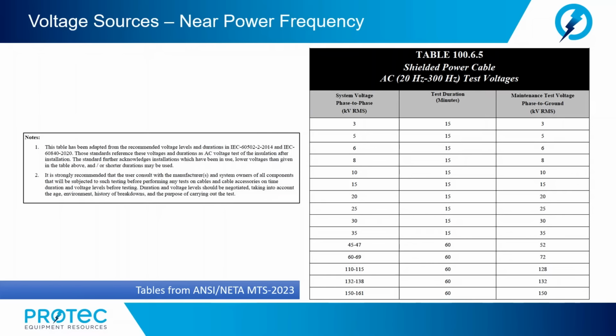And again, going back to the NETA tables that we find in the NETA literature, when we are dealing with medium and high voltage power cables, we do see that the near power frequency variety is called out in table 100.6.5, shielded power cables, AC testing, 20 Hz out to 300 Hz test voltage. This table is designed for the frequency-tuned near power frequency resonant test sets. And the test is typically called out to be 15 or 60 minutes at maximum voltage on individual or group cables in accordance with the manufacturer's published data.